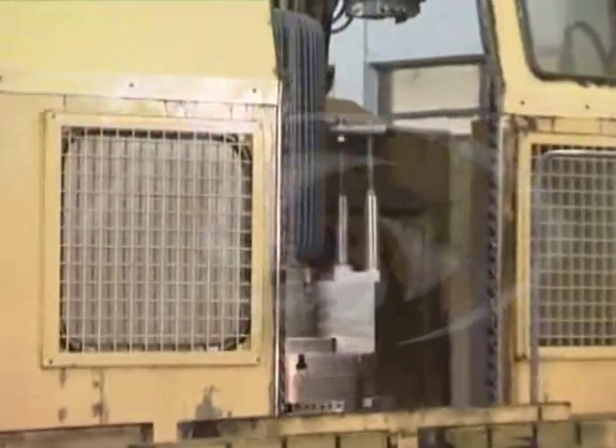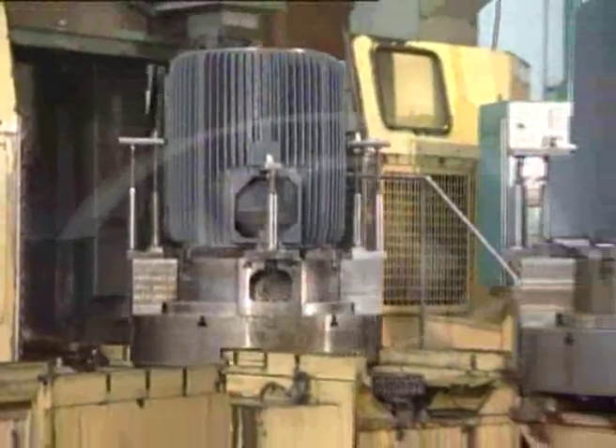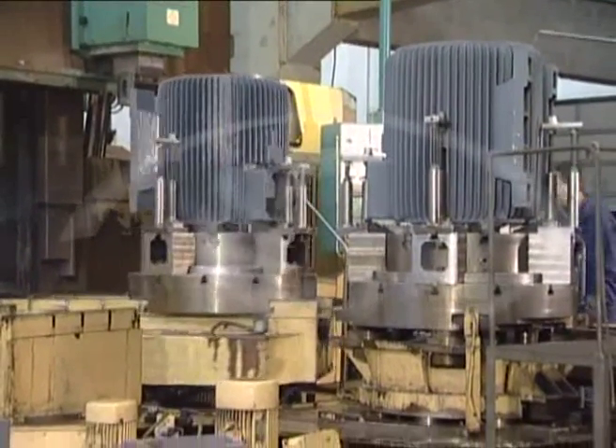The cast iron motor frame passes through a number of machining operations. The frame is clamped to this vertical turning machine. Upon machining of the front end spigot, the stator housing is machined in fine tolerances and finished by machining of the back end spigot. They are machined in one clamping in order to obtain the concentricity when components are assembled.